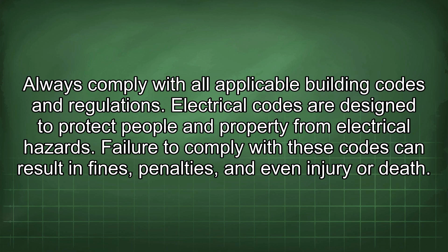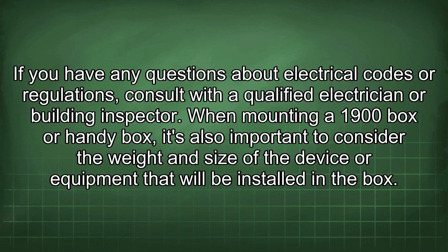When mounting a 1900 box or handy box, it's also important to consider the weight and size of the device or equipment that will be installed in the box. Heavier items may require additional support, such as using a larger box or adding blocking between the studs.